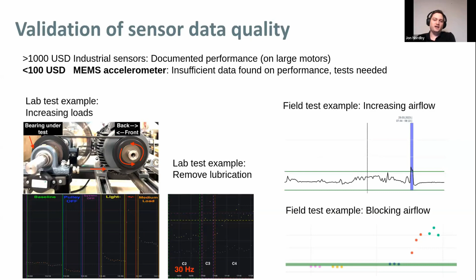We tested using MEMS accelerometer devices, and since we couldn't find great data on how well these perform under realistic conditions, we did our own tests — both in the lab, where we could do destructive testing, and in the field, where we stress-tested real systems up to their safe operating parameters. We found that MEMS accelerometer sensors can detect a range of problematic conditions, such as shaft misalignment, bearing failures, unusually high loads, etc.